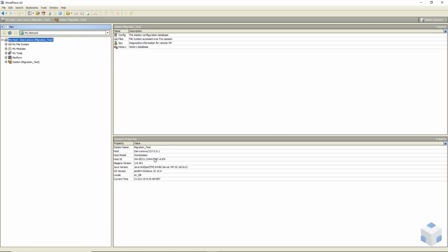Other pitfalls you have to look out for. Make sure you've got the same modules within your N4 install. What I'm saying is, if you've got any third-party drivers in there, you might want to go speak to them and see if you can get a newer version of the module. If not, you might have to remove it from the station, otherwise it will hinder the migration process. So let me just get down and show you how we're going to do that.